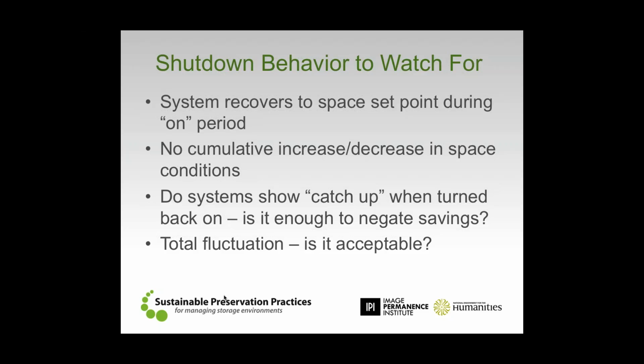And the other part, this is a question that we got an awful lot throughout the research, is, well, when we turn the system on the next day, do you use more energy trying to catch up to the condition that you may have lost overnight? Right? If we lost 2 degrees in space temperature overnight when we turn the system off, does that mechanical system then have to use more energy the next day in order to catch up and get those 2 degrees back? And the short answer really is, in most circumstances, no.